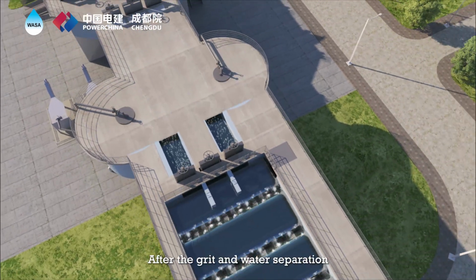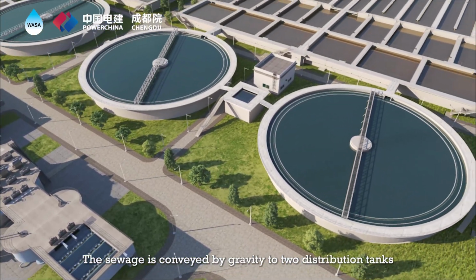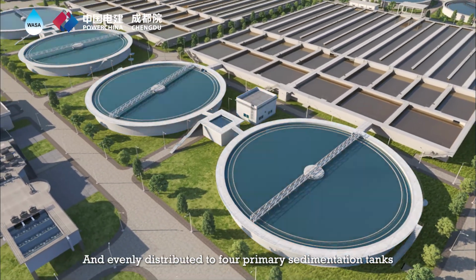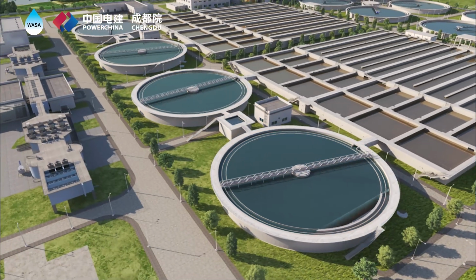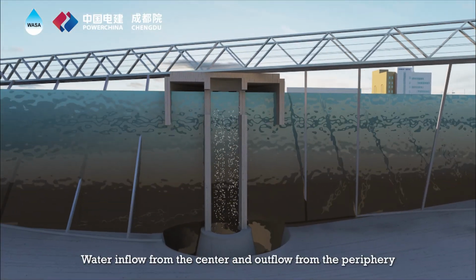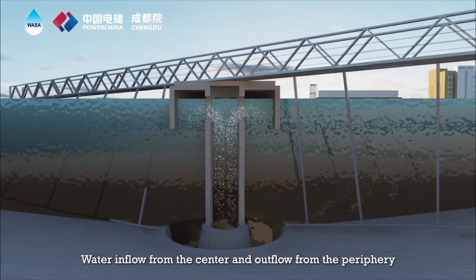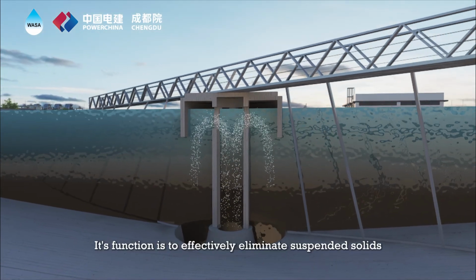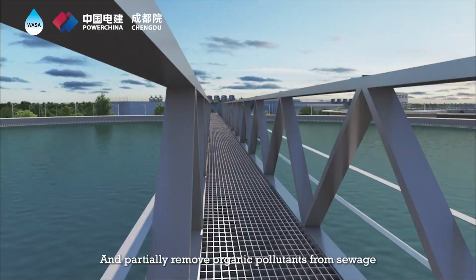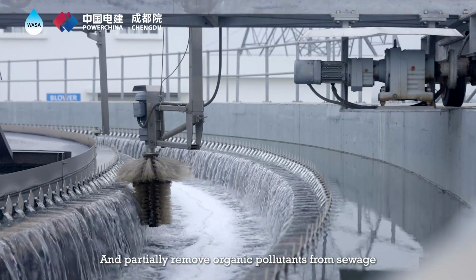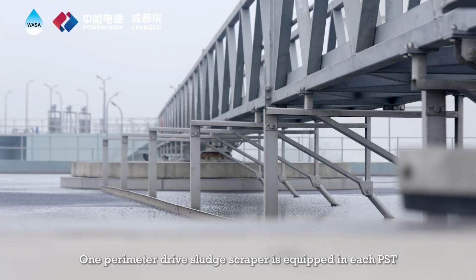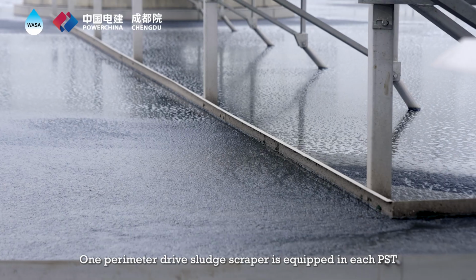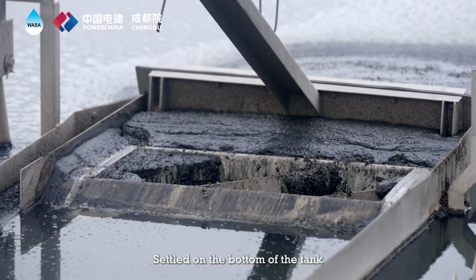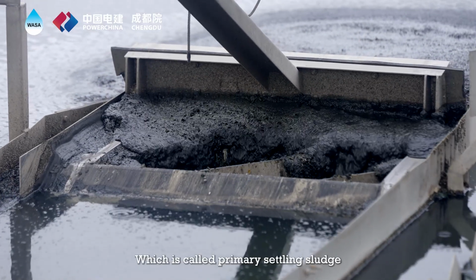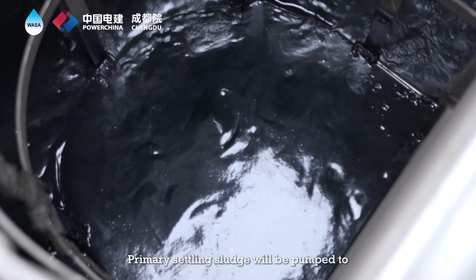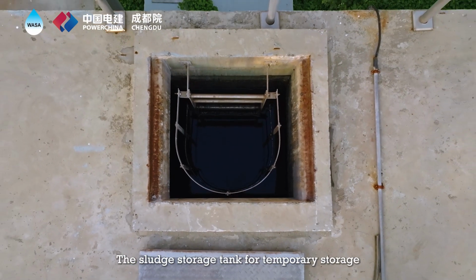After the grit and water separation, the sewage is conveyed by gravity to 2 distribution tanks and evenly distributed to 4 primary sedimentation tanks. The PST is a circular tank with water inflow from the center and outflow from the periphery. Its function is to effectively eliminate suspended solids and partially remove organic pollutants from sewage. 1 perimeter drive sludge scraper is equipped in each PST to collect the suspended solids settled on the bottom of the tank, which is called primary settling sludge. Primary settling sludge will be pumped to the sludge storage tank for temporary storage.